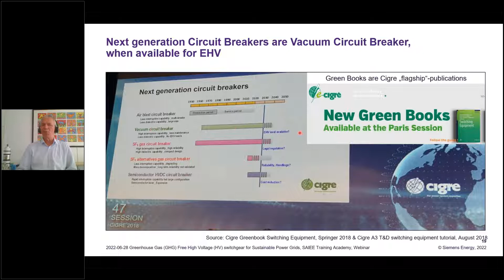The latest technology, the lowest line here, is the so-called semiconductor high voltage HVDC circuit breaker, which started a few decades ago. The problem right now is that semiconductor technology has very high losses. That's why, from our perspective, semiconductor high voltage circuit breakers will not be realized within the next 30, 40, 50 years. So looking at all the technologies, vacuum circuit breaker technology, from our perspective, is the future.